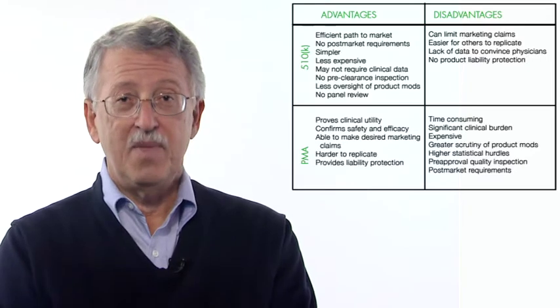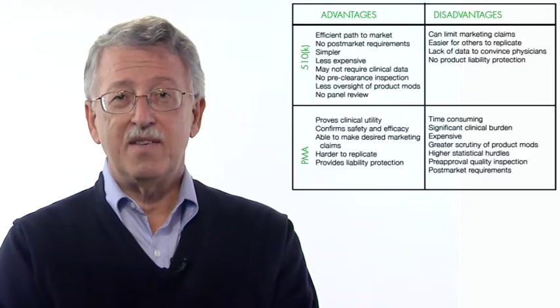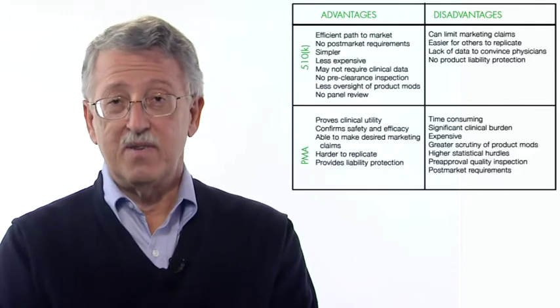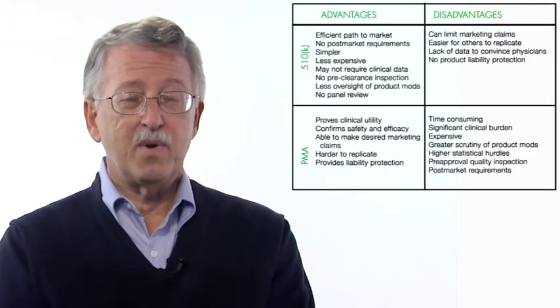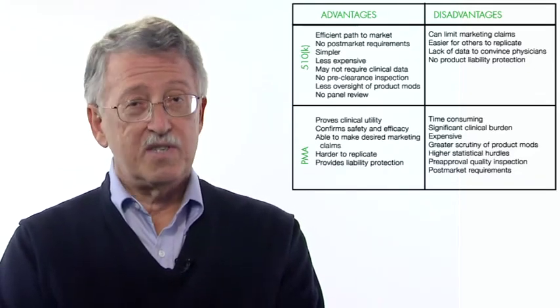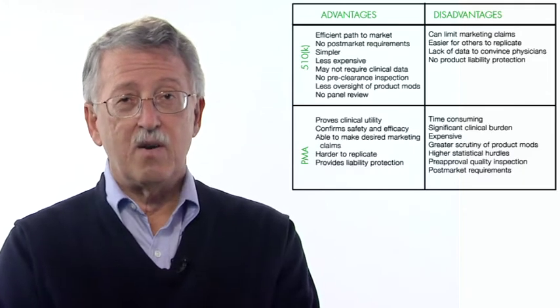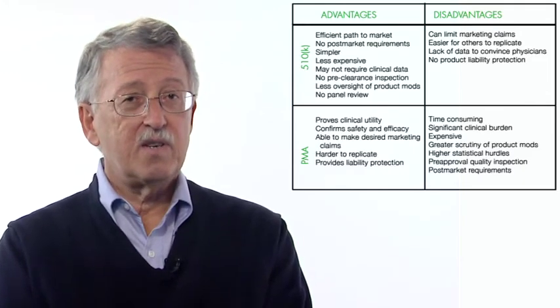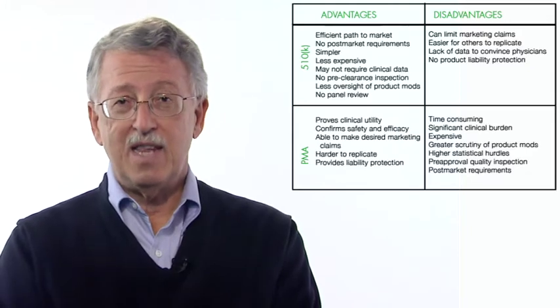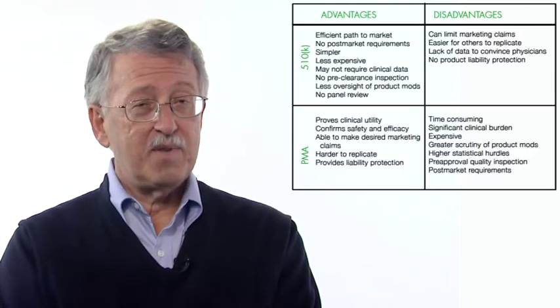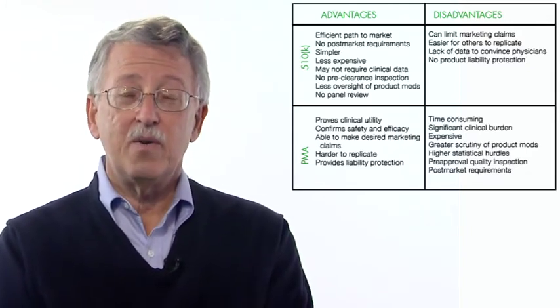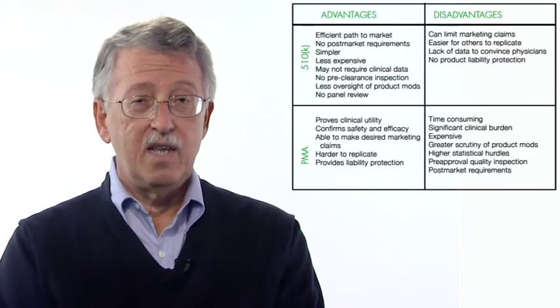For example, it's an efficient way to get a product to market that does not present a significant risk, where PMA might be required. Additionally, there's no requirement for post-market studies that are applied to 510K clearances. Usually, it's a simpler and less expensive application that needs to be submitted to FDA, even though it may or may not require clinical data.